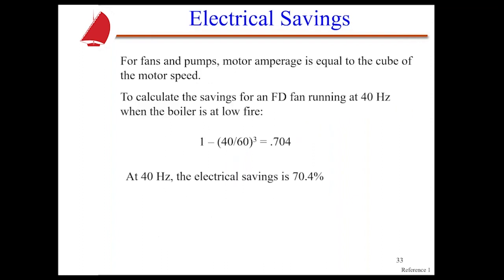And just to put it in perspective, here's a nice chart that shows you how much better you can control, because the horsepower savings is just monstrous. So if we're coming off of synchronous speed at 60 hertz and coming down to, for instance, 40 hertz, we can save about 70% of our electrical use. This is a huge deal. Now, obviously, with variable speed drives, how much you can turn down that burner depends on the burner design. And again, this is where the burner manufacturer can give you some good rule of thumb. Some, 50 hertz will be about a minimum. Some can go down even lower than 40 hertz. It depends on that particular design. And I would encourage you to talk with the burner manufacturer when you're commissioning one with a variable speed drive.